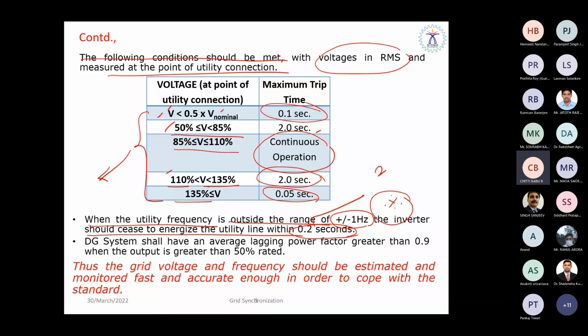So the inverter must be disconnected within 200 milliseconds. I mean, it's about 10 AC cycles, right? In addition to that, the renewable energy or distributed generation system shall have an average lagging power factor of 0.9 when the output is greater than 50% of the load. So in addition to the previous requirements, this also has to be met. This is also included in the grid connection requirement.